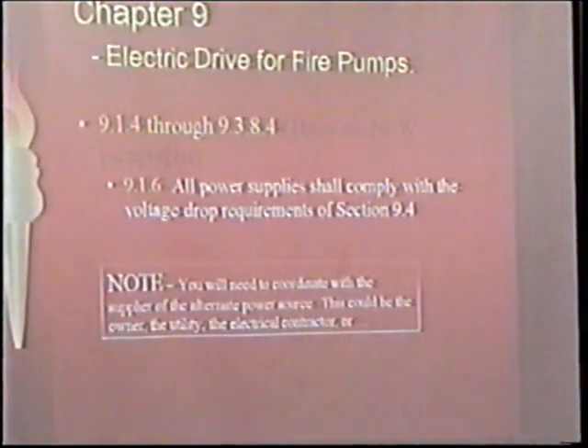This is another biggie. If you're dealing with a job that has an automatic transfer switch, you need to talk to your electrical contractor or the general and find out who's supplying the generator set. Because generator sets typically are not sized for standby duty with a 15% voltage drop requirement. They're going 30, 35, whatever they can buy with. Now, if it's a big facility, so that they're going to take the whole facility on, you probably don't have to worry about it. But if they're marginally sized, and they're going to take the fire pump on, and they're going to shed some other loads in the building in order to carry it, might be an issue.